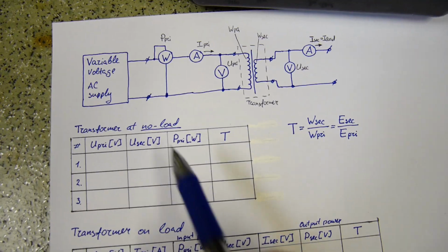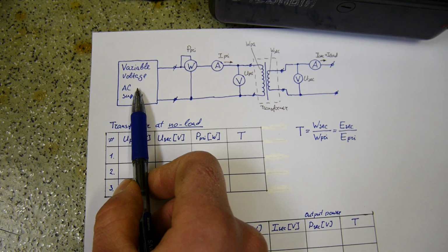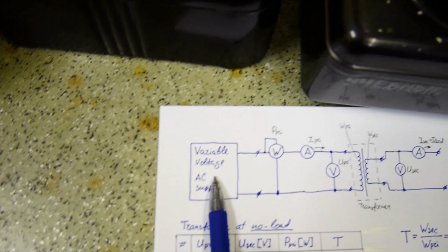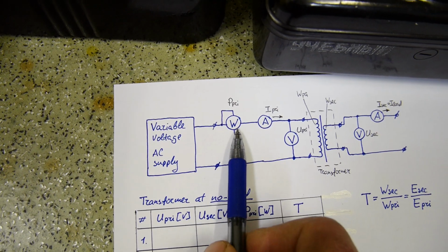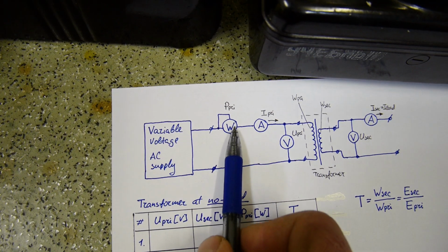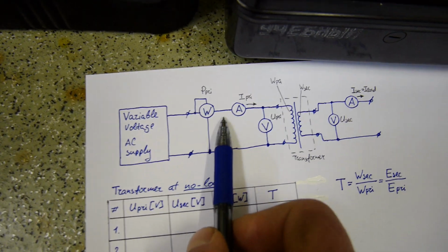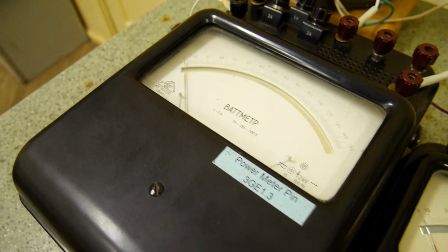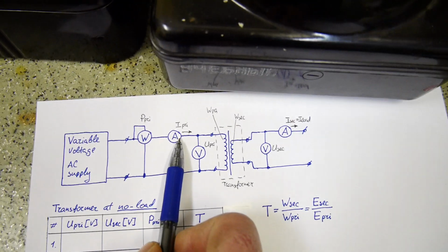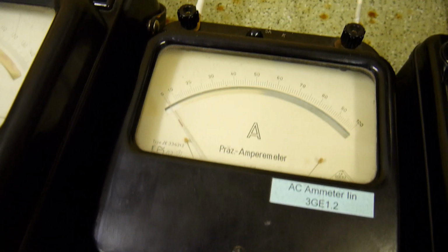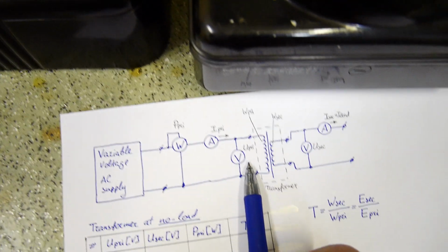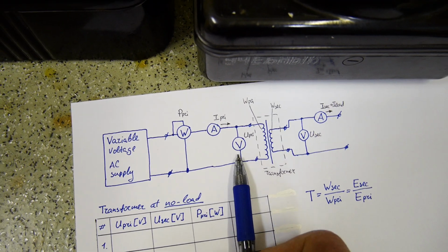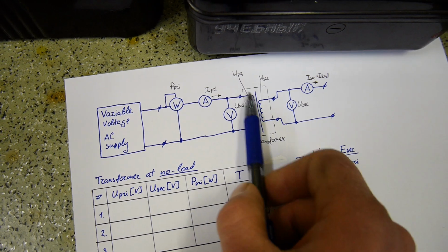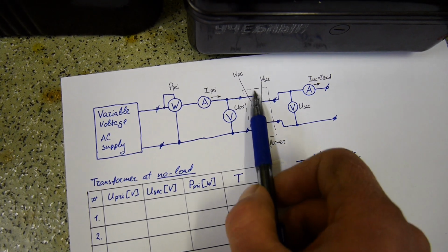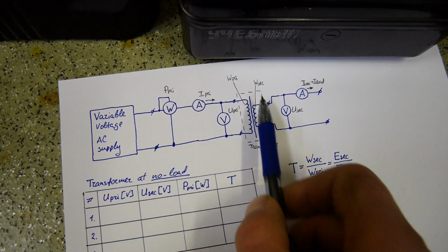On the schematic we can see variable voltage supply, this one, followed by wattmeter, power meter, which measures only active or real power in watts, this one, followed by ampere meter, this one, and also the voltmeter, which is attached here and which measures the voltage which is applied to the primary winding of a transformer.